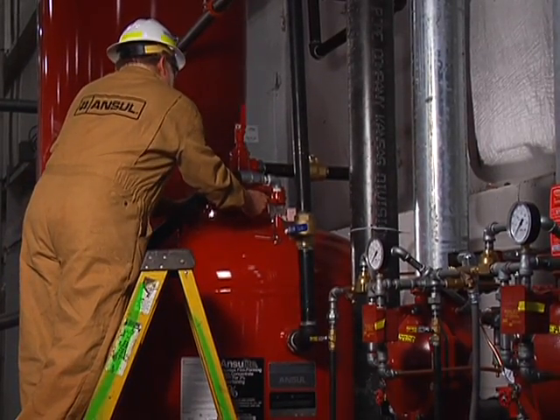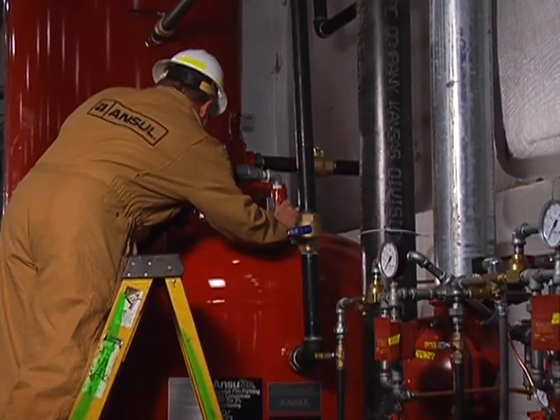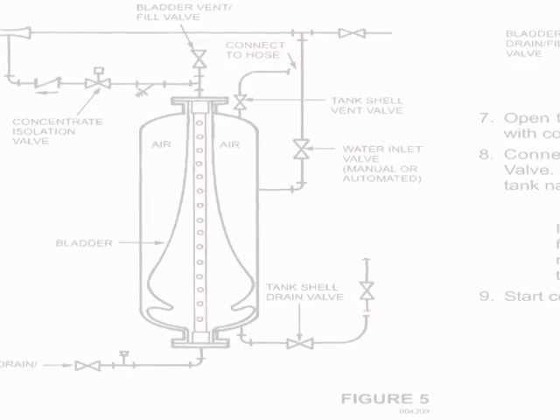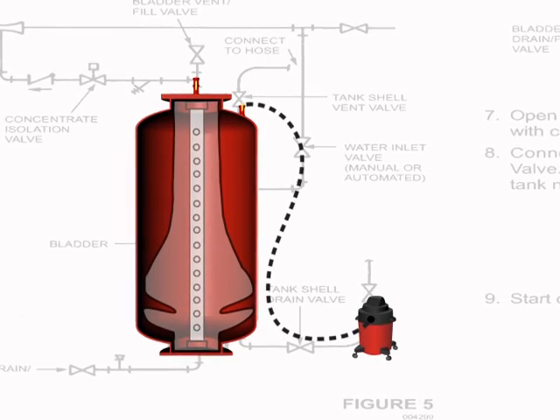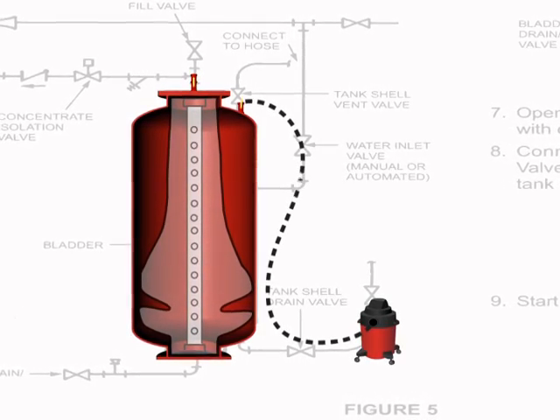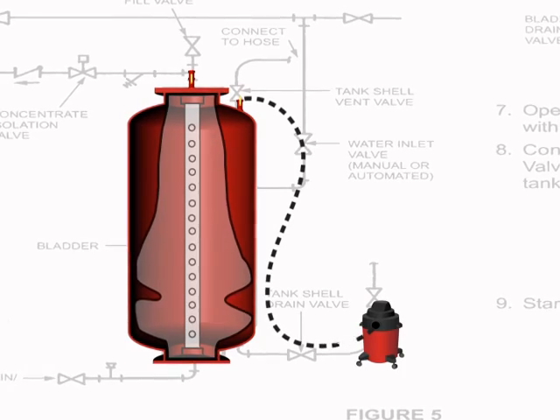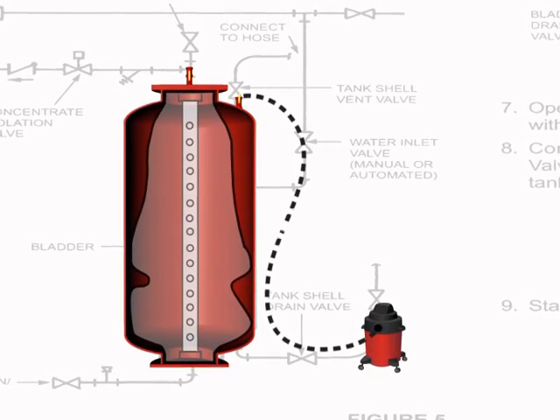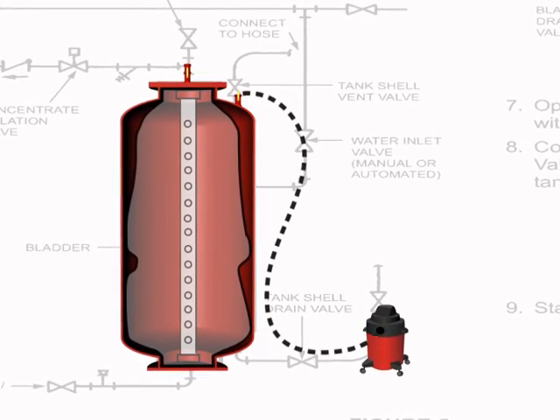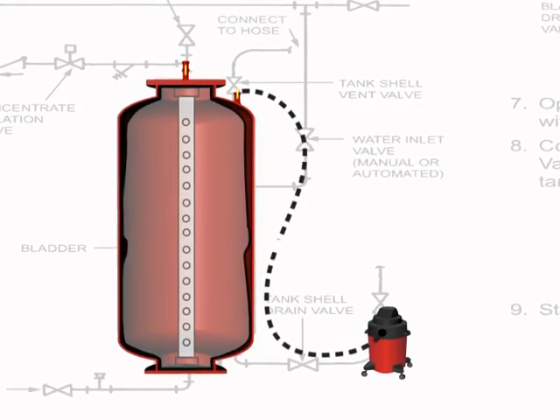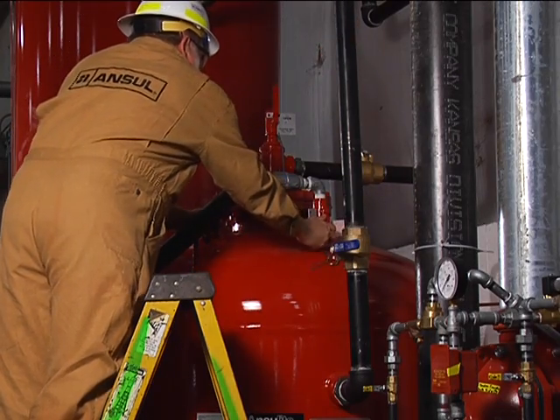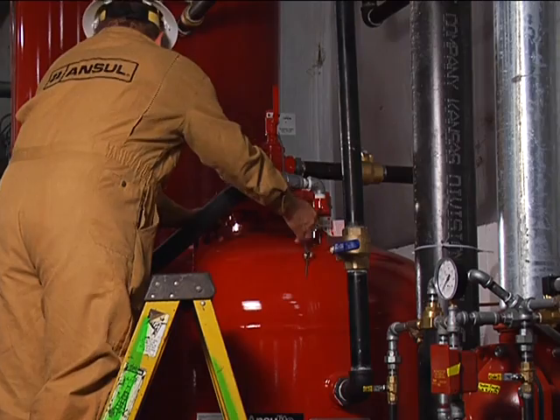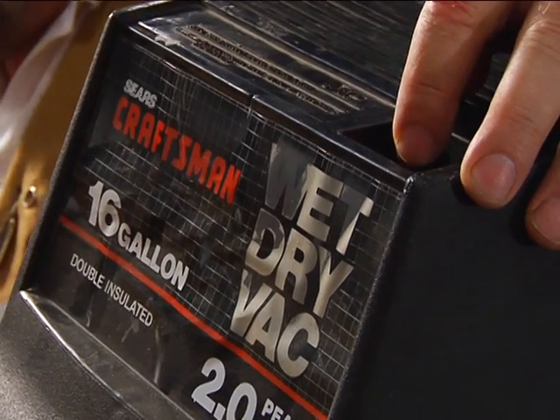Once you've activated the vacuum, open the tank shell vent valve to pull the air out between the bladder and the tank shell, which will pull the bladder out to the tank shell wall. Once you've heard the change in pitch from the vacuum, the bladder is completely pulled out to the tank shell wall.